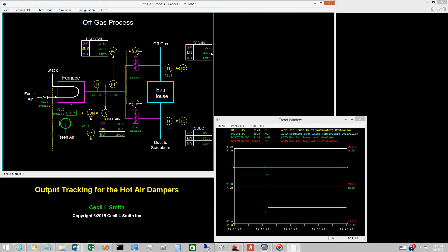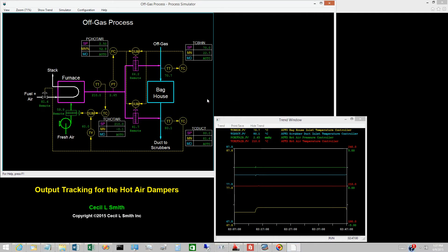To demonstrate that the transition back to automatic control is bumpless, switch the hot air damper to baghouse inlet to remote. The transition is smooth and the baghouse inlet temperature controller quickly restores the temperature to 70 degrees Celsius.